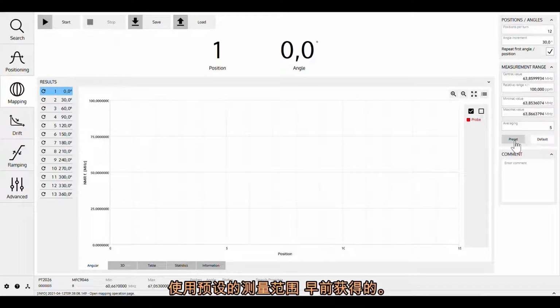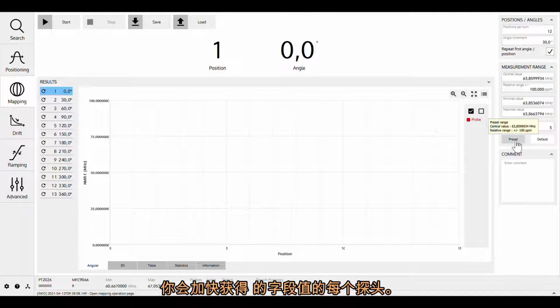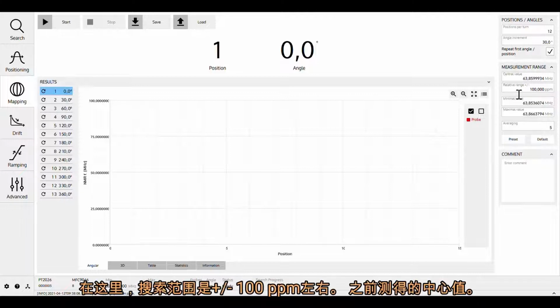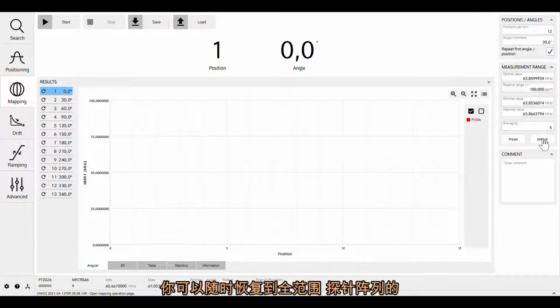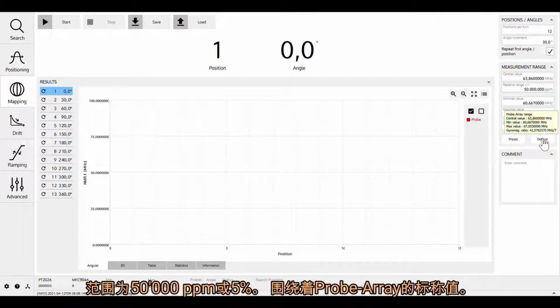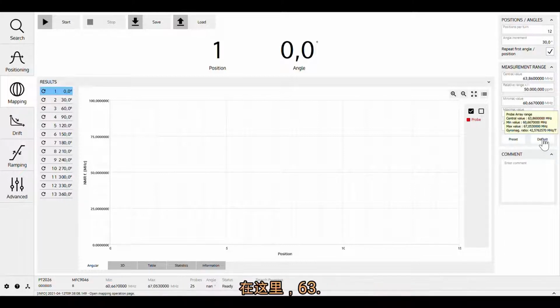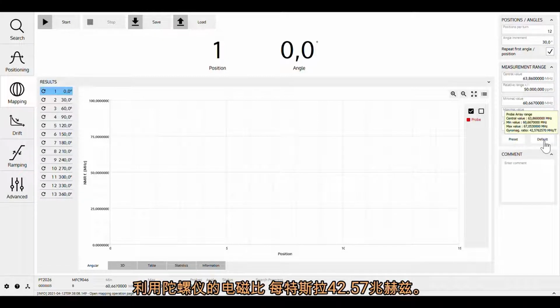Using the preset measurement range acquired earlier, you will speed up the acquisition of the field value of each of the probes. Here, the search range is plus or minus 100 ppm around the central value measured earlier. You can always revert to the full range of the probe array with a range of 50,000 ppm or 5% around the nominal value of the probe array. Here, 63.86 MHz or 1.5 Tesla, as can be calculated using the gyromagnetic ratio of 42.57 MHz per Tesla.